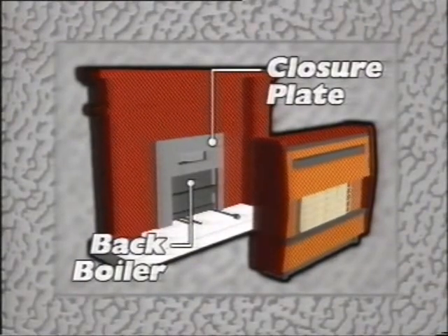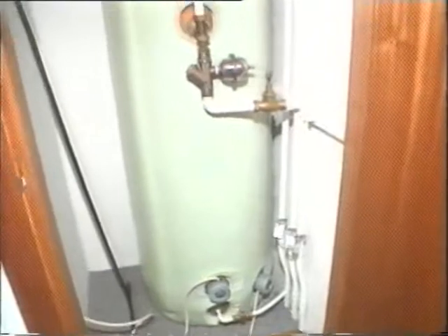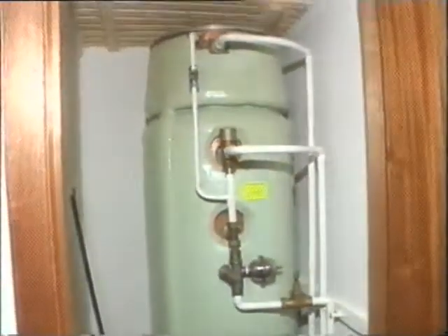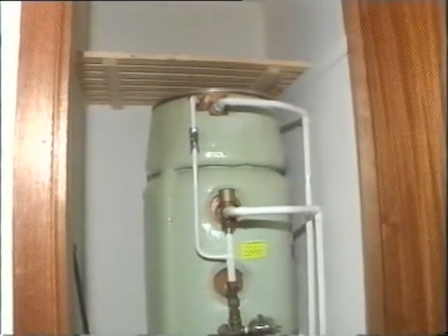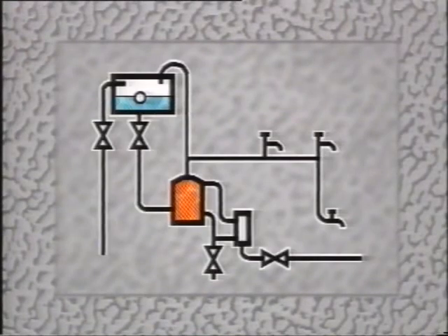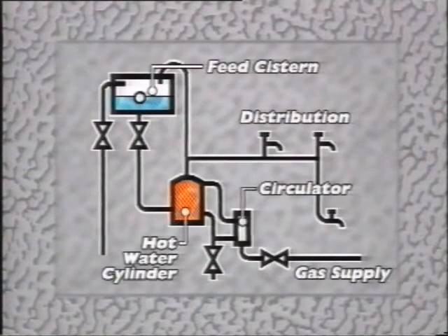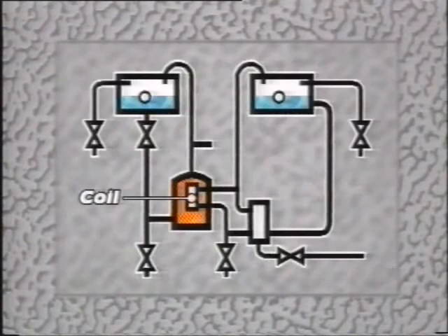They can be connected to the storage tank either directly or indirectly. In the direct system, the water heated in the circulators is in direct contact with the hot water supply to the draw-offs. In other words, it's the same water. If there's a danger of scale being formed, an indirect system should be used instead. In an indirect system, the circulator water isn't the same. Instead, a coil fitted in the hot water cylinder transfers the heat to the stored water.